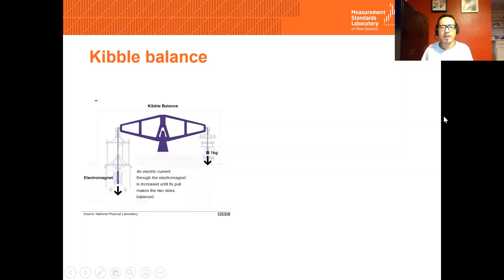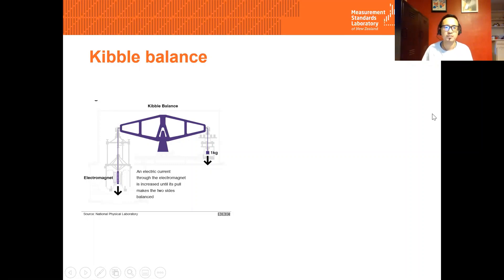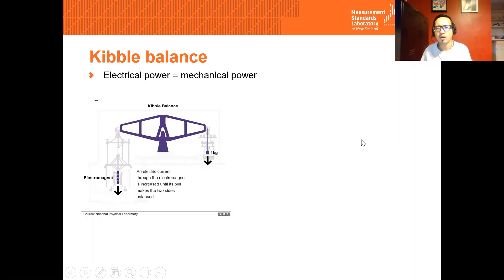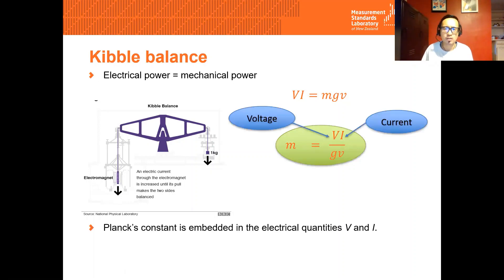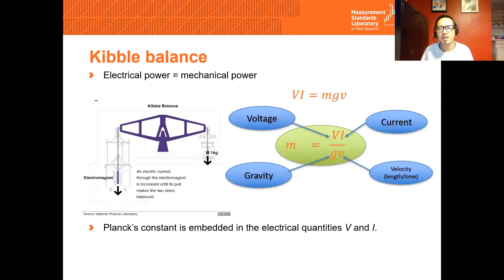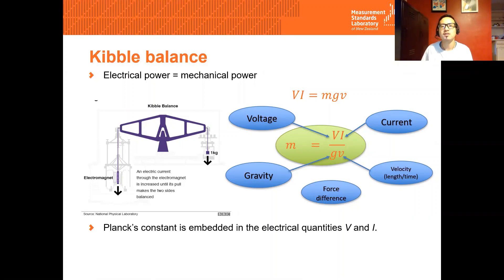This slide is a quick recap on the main principle of Kibble Balance. It is basically an apparatus to compare gravitational force on a reference mass with the electromagnetic force on a current-carrying coil in a magnetic field. From there, you can derive an expression where electrical power equals mechanical power when you operate the Kibble Balance in two different modes. This means by measuring quantities like voltage and current — where Planck's constant is embedded — and gravity and velocity associated with careful force balancing, we can obtain the mass value. The main challenge, of course, is that we have to do this with great precision and simultaneously.